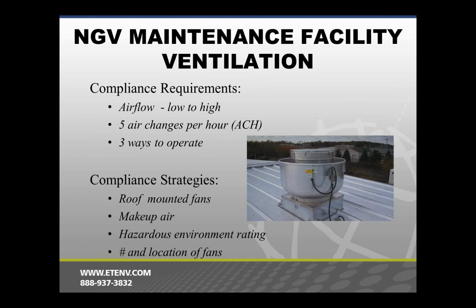So with this purge ventilation, as I'm calling it, this is what we would do on a gas detection or continuously, depending on how you want to comply. But that airflow is from low to high. You want to exhaust from the ceiling, which is opposite your normal occupancy ventilation, at 5 air changes an hour. And there are 3 ways to operate it. You can operate it continuously, or interlock it to gas detection, and for CNG vehicles, there's a 3rd way, and that's interlock to the lights or a while-occupied type of ventilation.